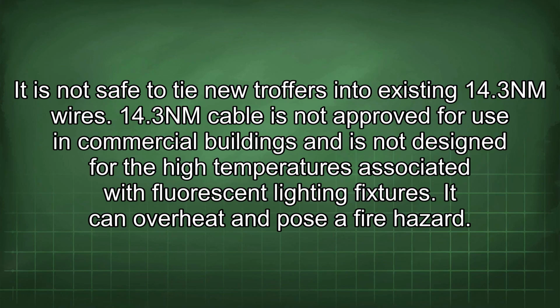It is not safe to tie new troffers into existing 14.3 NM wires. 14.3 NM cable is not approved for use in commercial buildings and is not designed for the high temperatures associated with fluorescent lighting fixtures. It can overheat and pose a fire hazard.